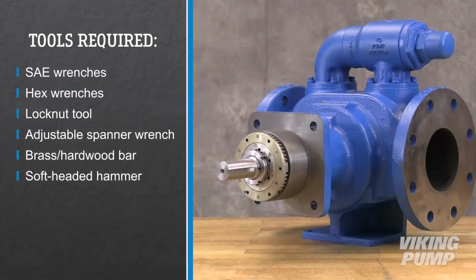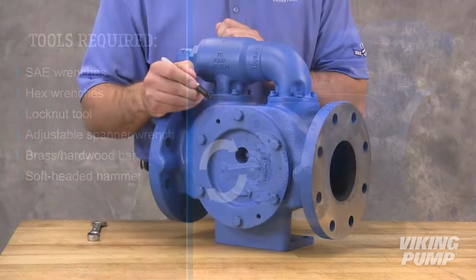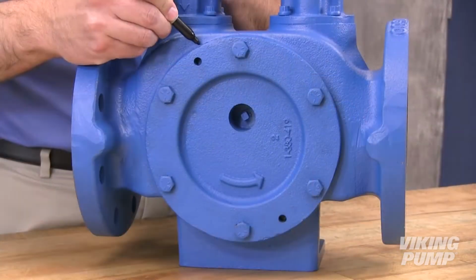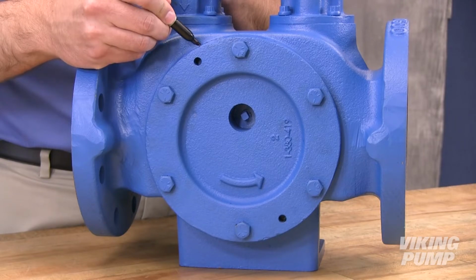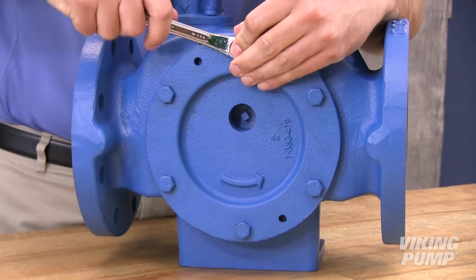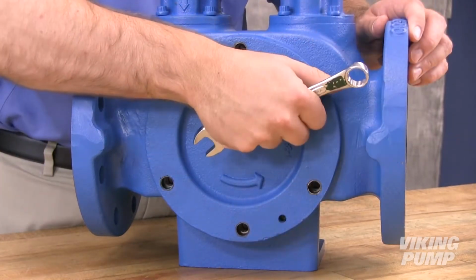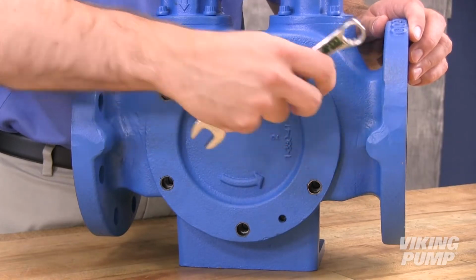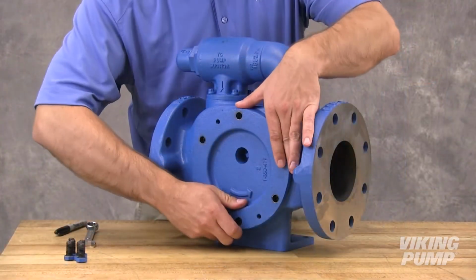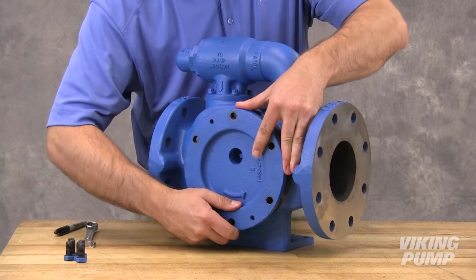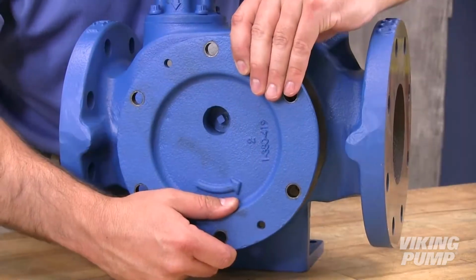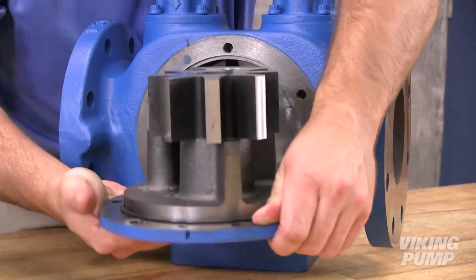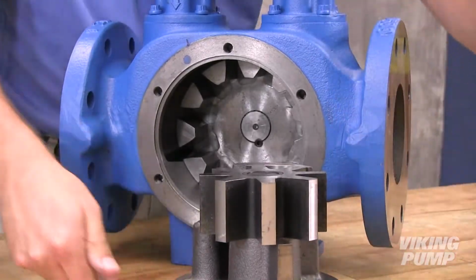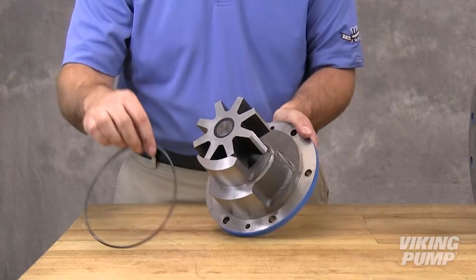To begin, drain the pump of any residual liquid. Turning the shaft will help expel any liquid trapped in the gear teeth. Mark the head and casing before disassembly to ensure proper reassembly. Loosen and remove the head cap screws. Remove the head by tilting it backward to prevent the idler from falling off the idler pin. Remove and discard the head O-ring.